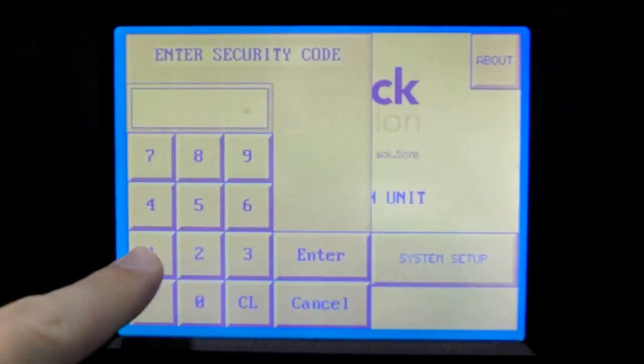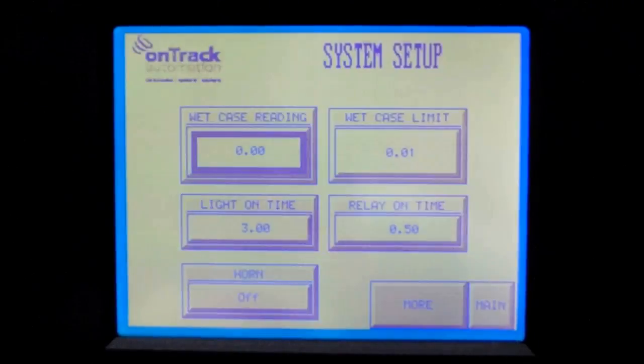The supervisor interface is password protected and allows for total customization of the Wet Case Detection unit. The supervisor can adjust such things as the conductivity threshold, how long the light stays on, how long it takes for the unit to reset, and whether to turn the light on.